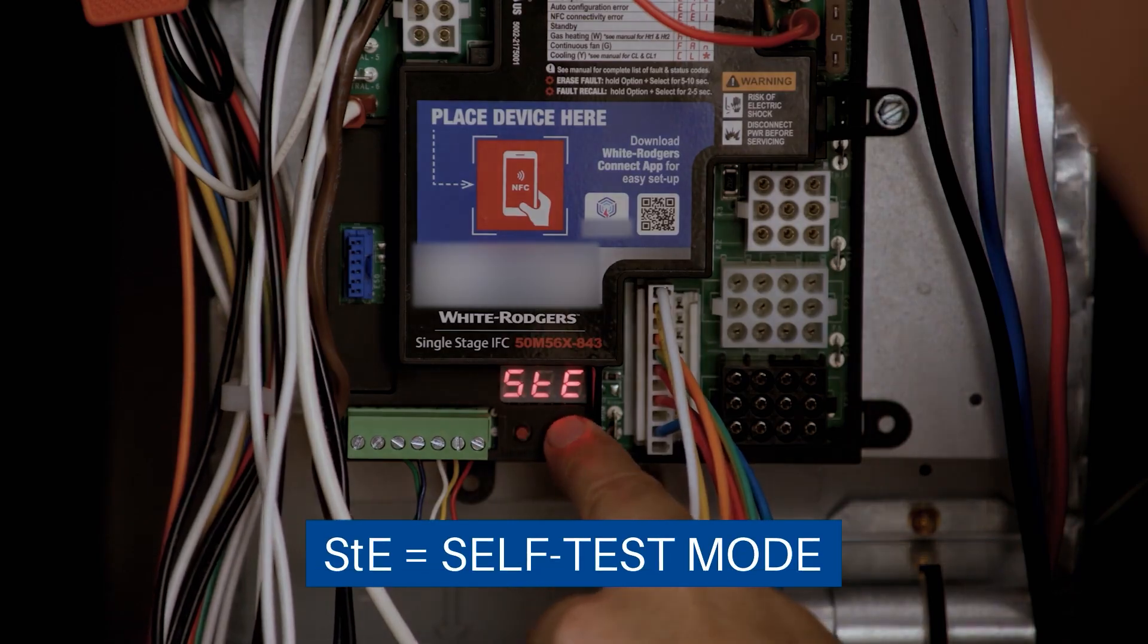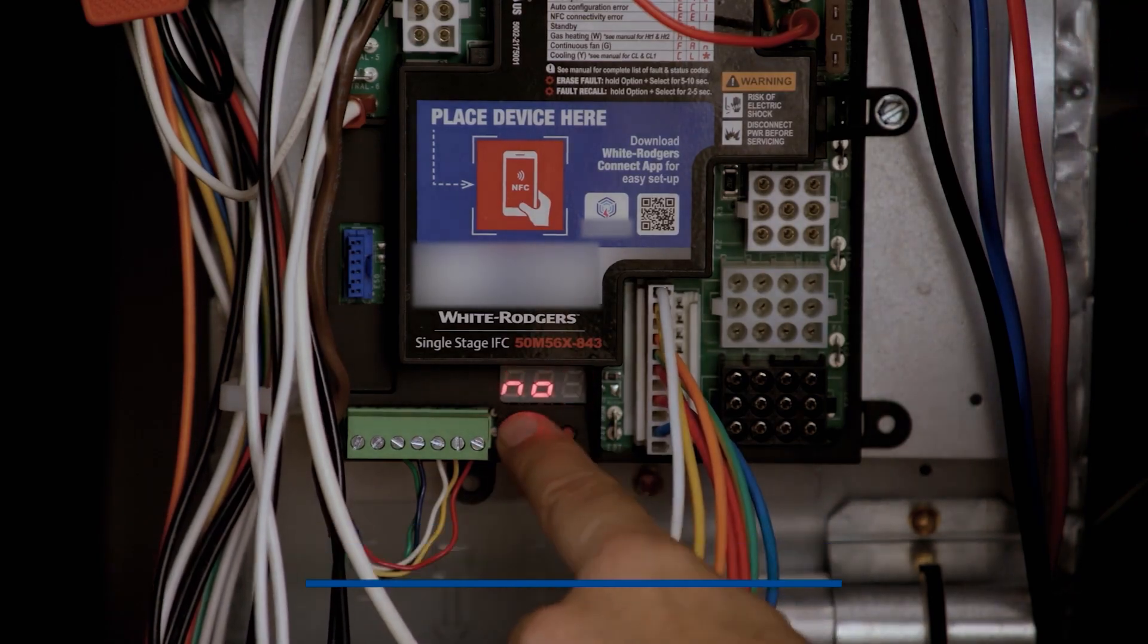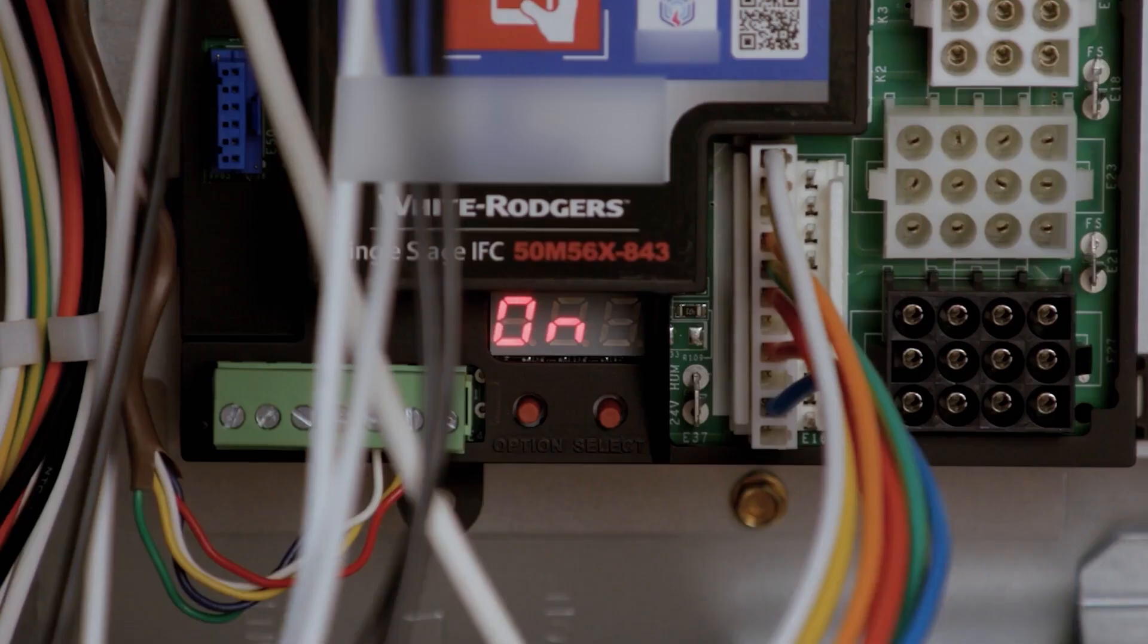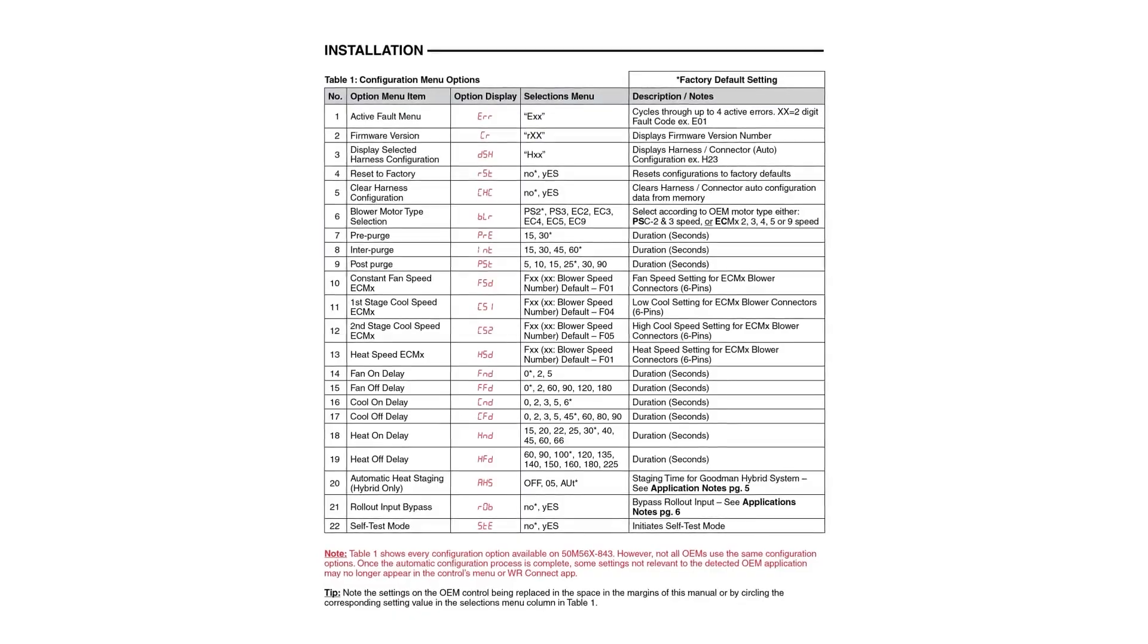In the self-test mode, most components can be tested without a call for heat. The display will show active status, flame current, and any error codes.